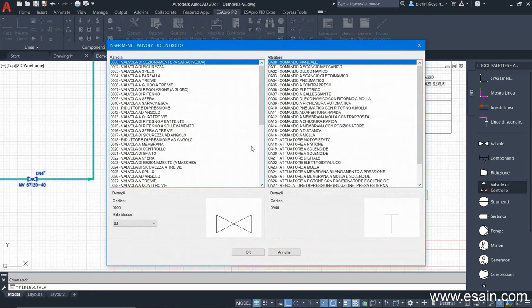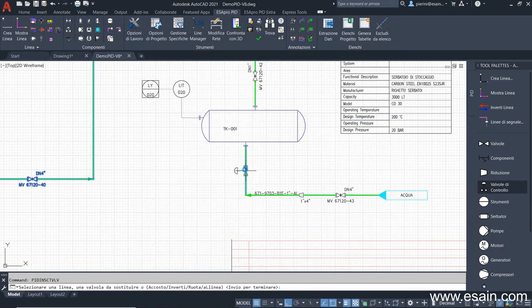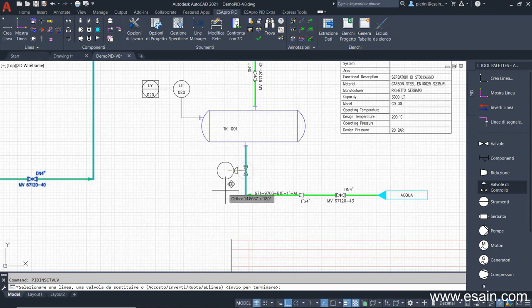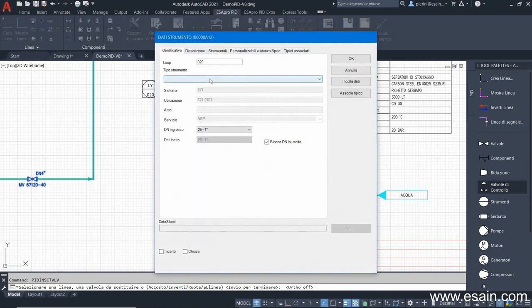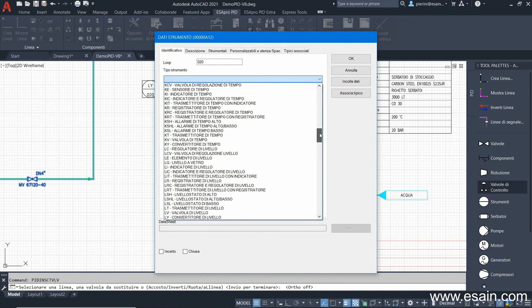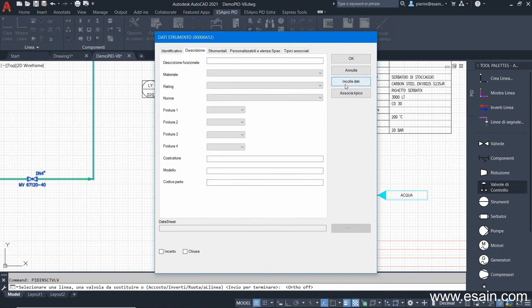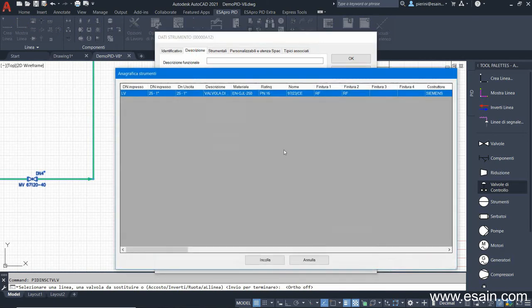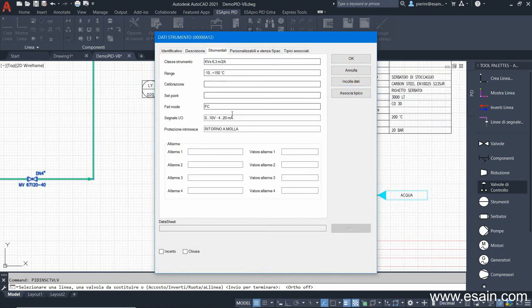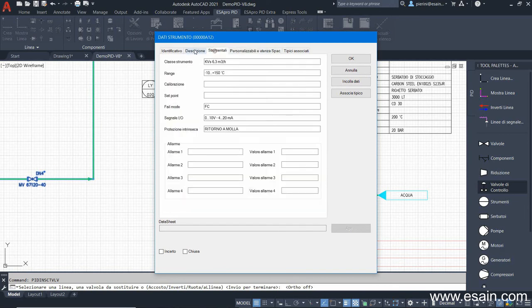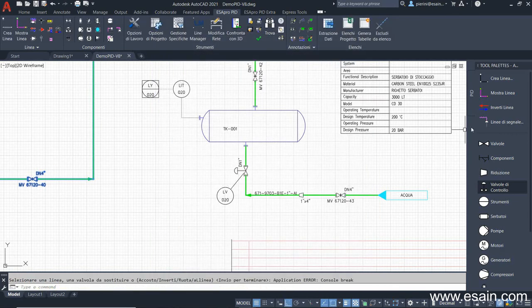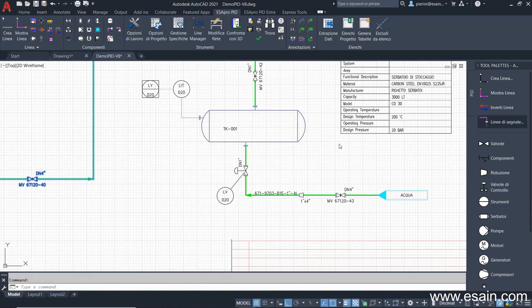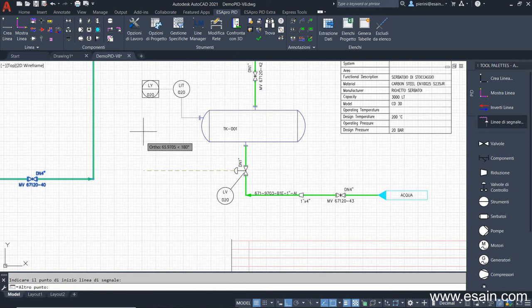Close the loop with the control valve. Here we have the possibility to choose a set of actuators. We place the balloon that contains the item name and assign a tag to this instrument. It will be a level valve. In this case, the location is taken automatically. And I can use my Excel table to define my object. It's a valve provided by Siemens and besides the standard fields, there are a set of spare fields named custom fields. We connect the valve with the pneumatic type line. And at this point, the loop is complete.